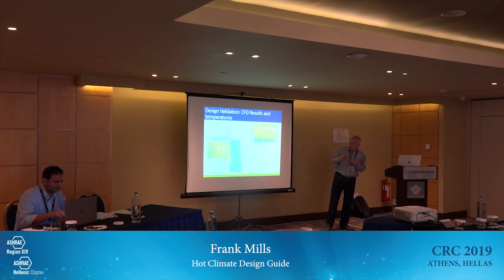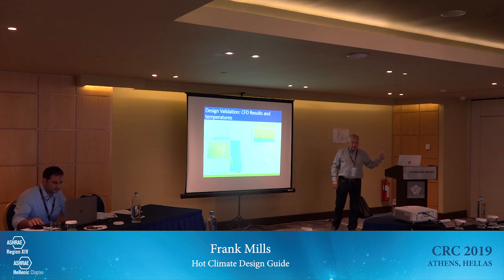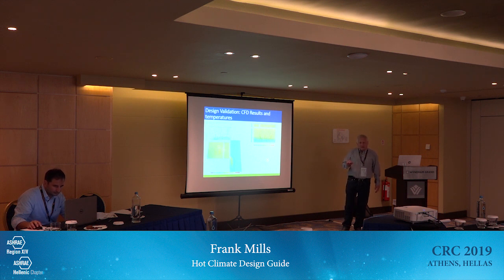So that's one bit of feedback I'll put in the guide. In my design I had them in both places, but in one of the projects there was a problem and the contractor didn't put them in here. He said, do we need them? I said, yeah, we need them. We didn't put them in. Those rooms are less easy to control than the other buildings where we control that inlet and outlet. Okay.